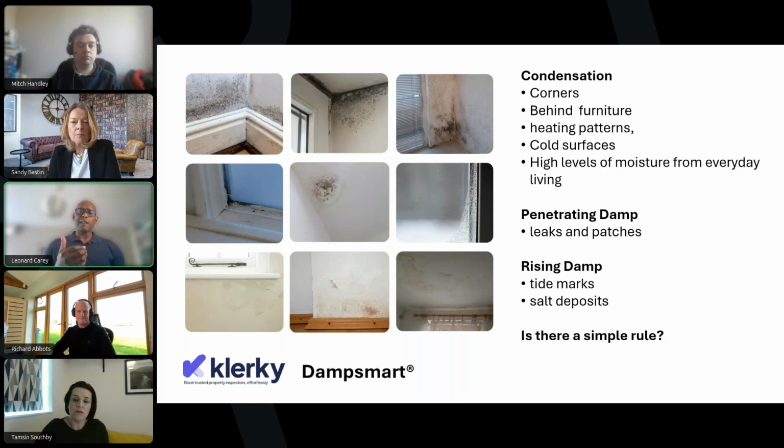When we went in and did the survey, with all the sensors and the analysis, we discovered that the tenant was ventilating the property. But because they're quite near a very humid environment, with trees and the river, no matter what they were doing, the moisture levels outside weren't really helping with the drying effect inside.